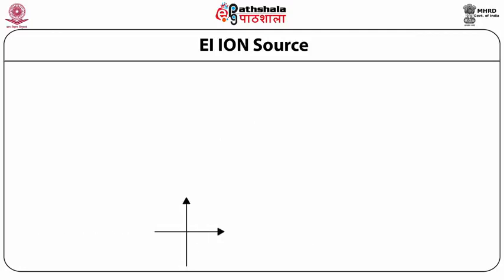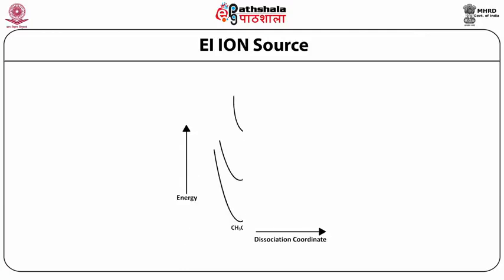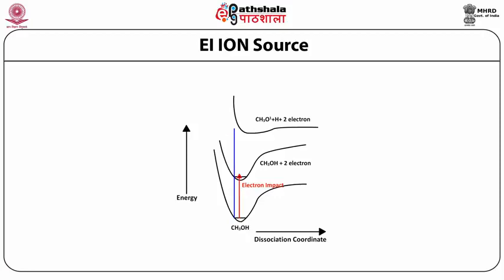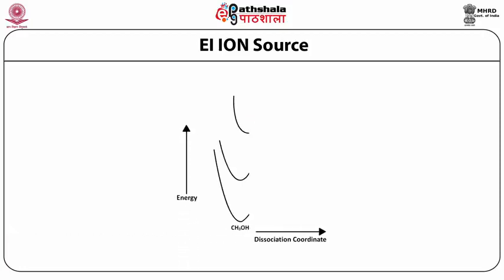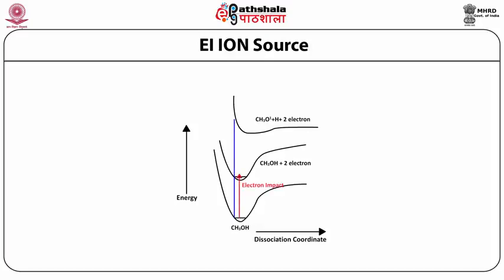If you are working in positive ion mode, only positive ions will be recorded. If you are working in a negative ion mode, only negative ions will be produced and then directed to the analyzer and finally detected by the detector of a mass spectrometer. Of course, the entire system works under very high vacuum.